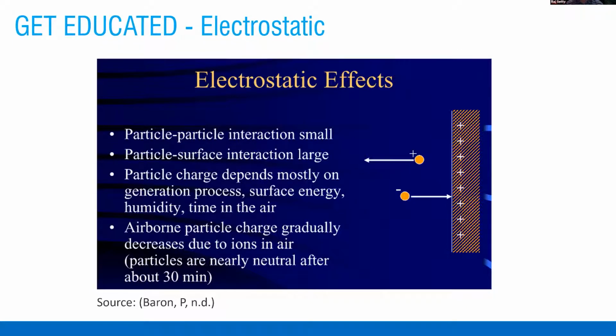So this is also bipolar ionization and a couple of other technologies in the general category of corona discharge. This is a great technology if you cannot change your filters, especially in those very small terminal units: PTACs, heat pumps, VAVs. It does improve your filtration. However, there is no correlation saying I have a MERV 8 filter, I will do a bipolar ionization and I get a MERV 11. There are no peer-reviewed studies stating that. They're all manufacturer data.